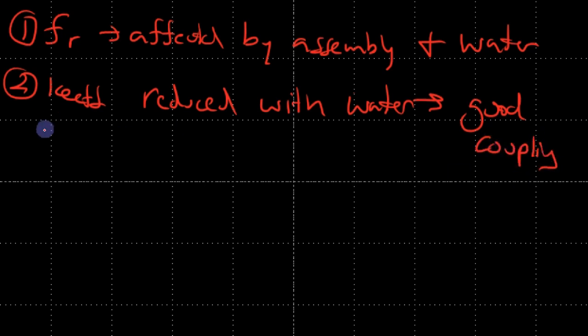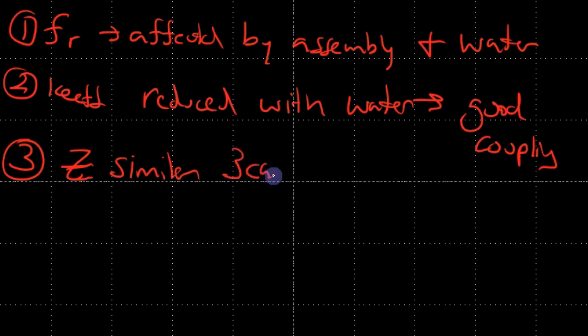I look at the other factors here, and the other factors are that the impedance is similar. The impedance is similar between the 3 cases. Similar meaning on the same order of magnitude, so it tells me that something didn't horribly go wrong, that the impedance became 1000. That means the transducer is not able to vibrate. The resonance frequency is completely shifted and the dynamics are completely changed. But now the dynamics are similar, except the boundary conditions vary slightly in order for us to propagate waves through the water.